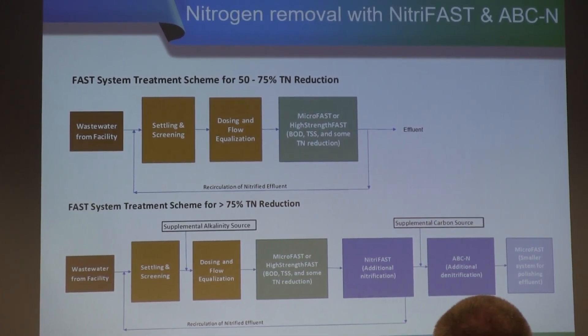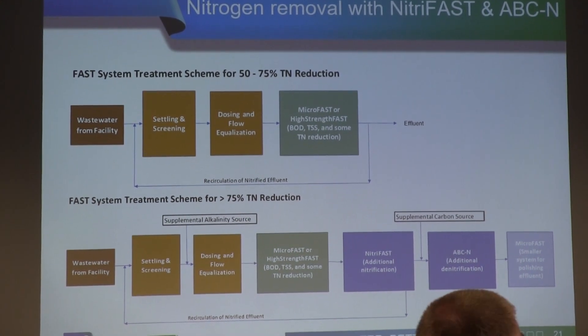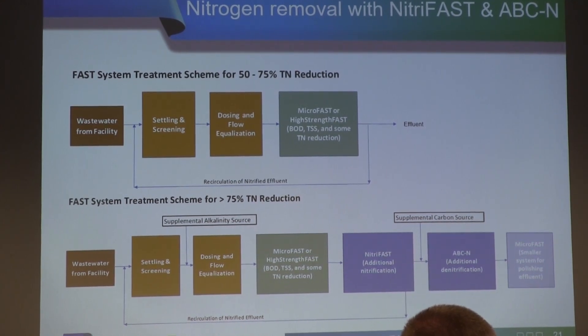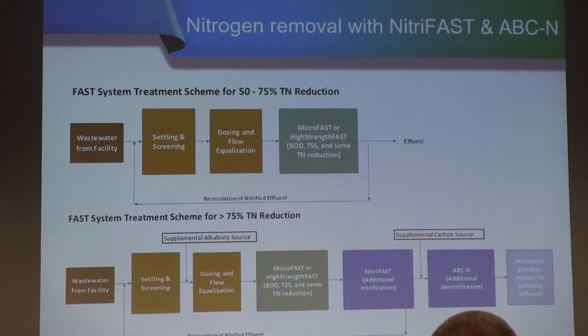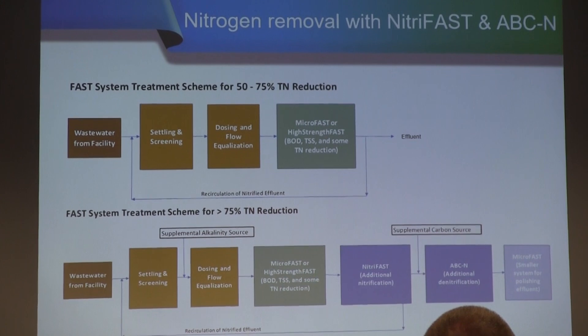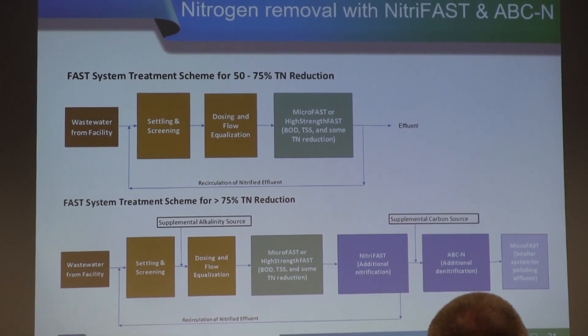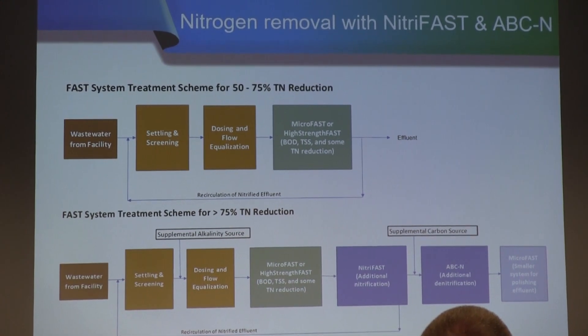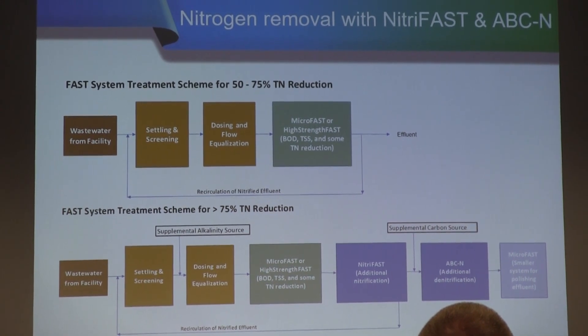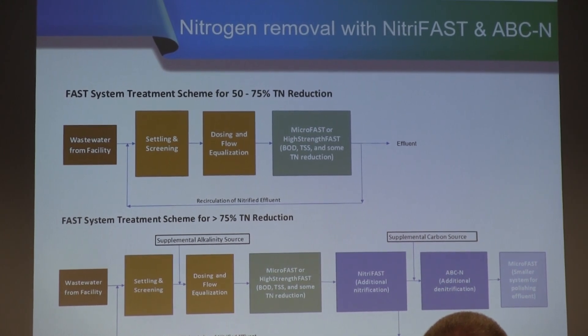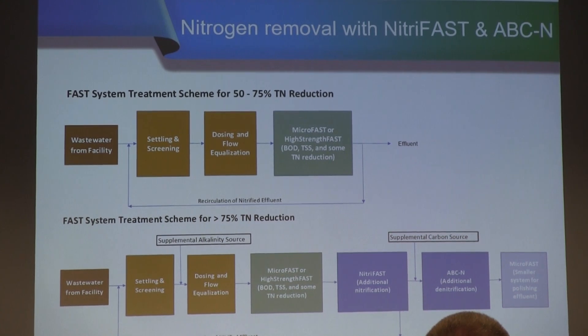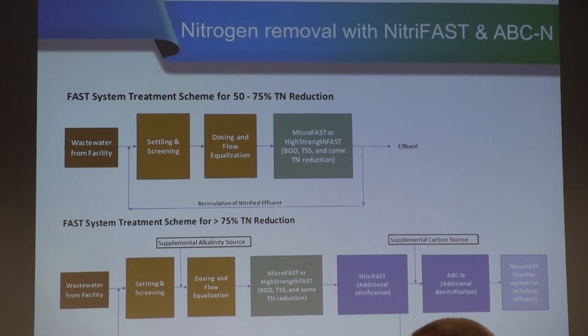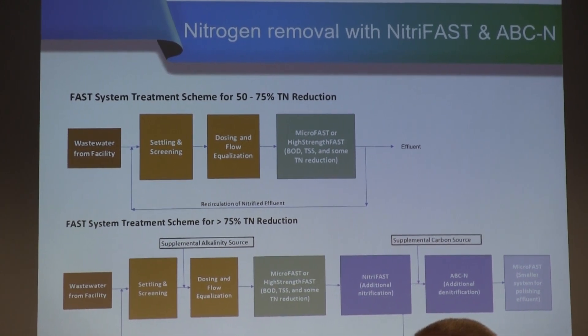When you need a higher percentage removal of total nitrogen, that's when NitriFAST and ABCN come into play. The treatment train below shows all the same steps as above, but now adds a NitriFAST step for complete nitrification, then that nitrified wastewater goes through the ABCN for denitrification — a post-anoxic process. The recirculation step is still there, placed right after the NitriFAST, not after the ABCN.